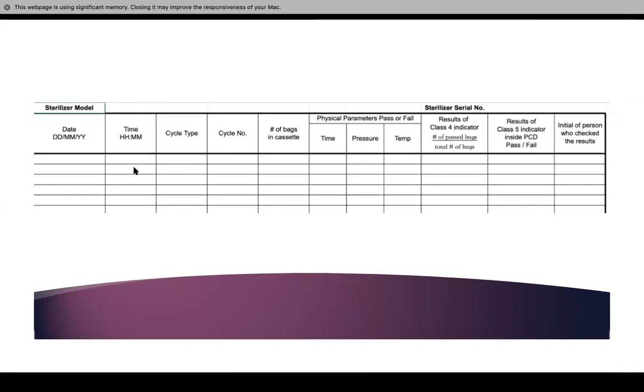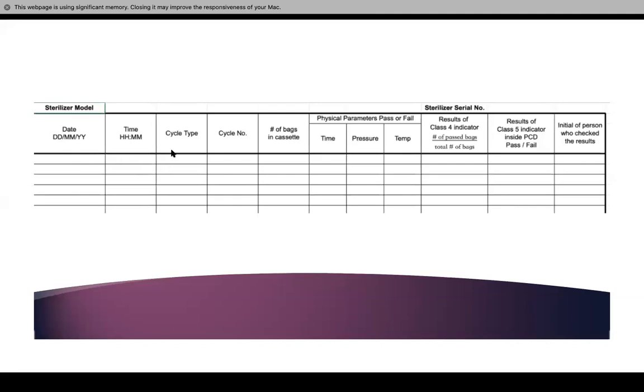This is what they look like. We have different logs for different cycles. For example, this one is the closed cycle — everything is pouched, labeled, and sterilized. We have to place the date, the sterilizer model, the date of the cycle, the time, and the cycle type — whether it is wrapped, unwrapped, or anything like that.